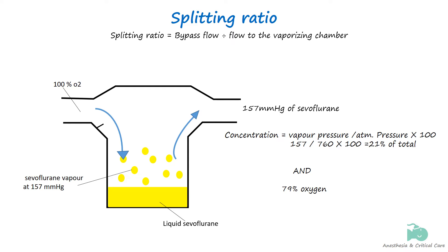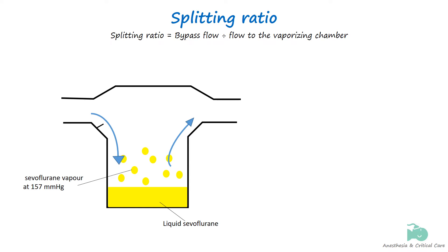This is way too much to use in practice. To lower its concentration, we need to split the fresh gas flow and only allow a proportion to go into the vaporizing chamber by making some gas bypass it.